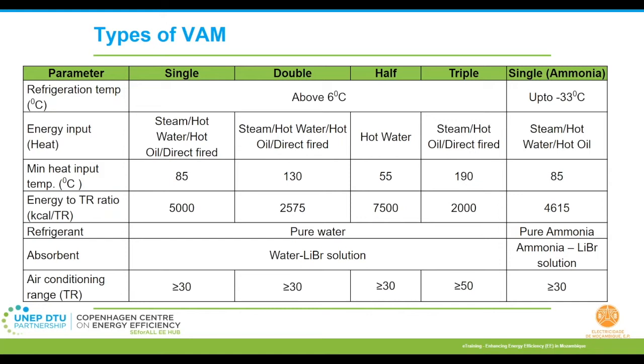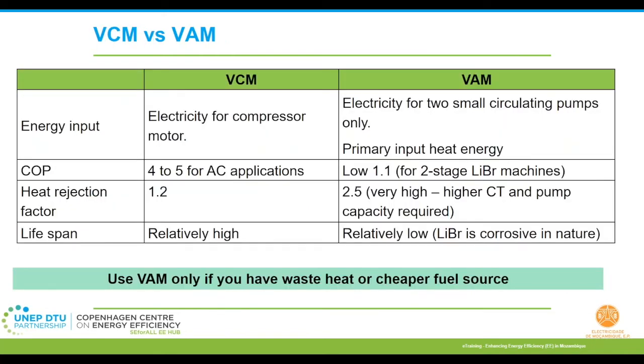This slide gives you the different types of vapor absorption machines, that is VAM, available based on your requirement, the heat source that is available, and the quality of heat that is available. I introduced VAM here so you can see its advantages and disadvantages, a comparison between two types of systems available under refrigeration and air conditioning. Looking at the energy input, conventional vapor compression machines, which can be as simple as air conditioning units in your homes or offices, or larger air cooled and water cooled chiller systems, mostly rely on electricity for operating the compressor motor. The VAM machines, on the other hand, have heat as the primary energy input.